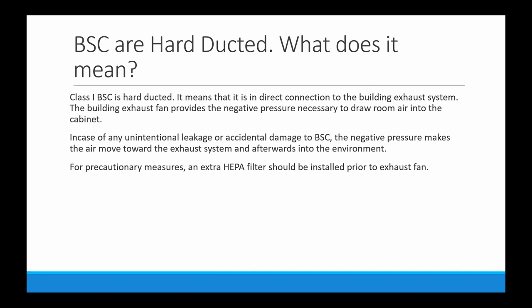A class one biosafety cabinet is hard ducted, meaning it is in direct connection to the building exhaust system. The building exhaust fan provides the negative pressure necessary to draw room air into the cabinet. In case of any unintentional leakage or accidental damage, the negative pressure makes air move toward the exhaust system and out to the environment. As a precautionary measure, an extra HEPA filter should be installed prior to the exhaust fan.